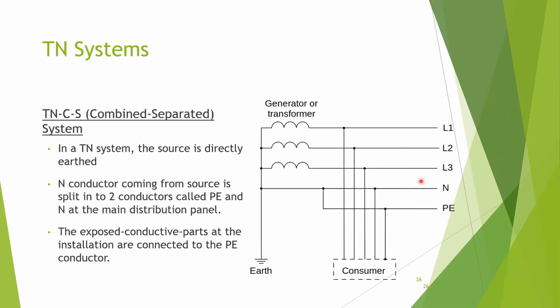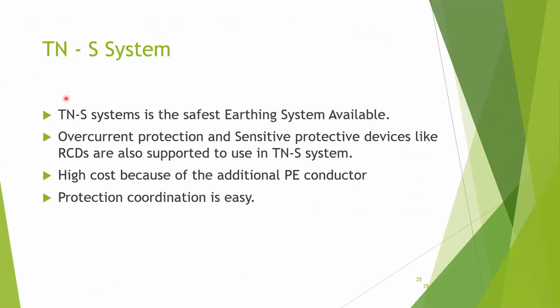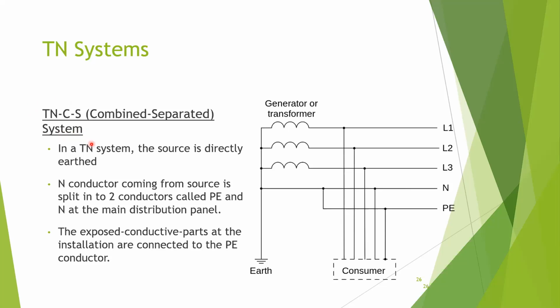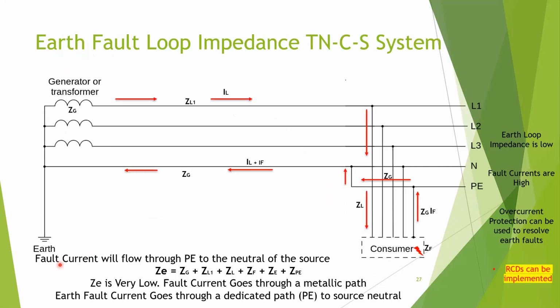So in here, the advantage is we can have the same protection level as TNS. This is the most optimum earthing system available because we can have all the features of TNS, safety, everything. So if you consider residual current protection, we can also have residual current protection because up to this point we can experience a difference. I will draw it next. Okay, TNCS system.